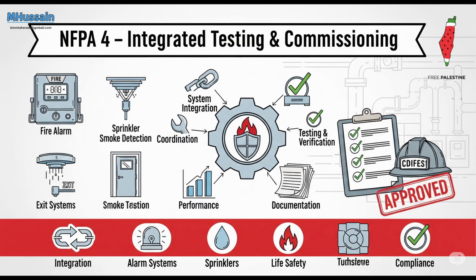And that's exactly what we're diving into today, a deep dive into NFPA 4, the standard for integrated fire protection and life safety system testing. This isn't just about individual components working in isolation. It's about making sure every single part of a building safety system works together seamlessly as one unified system. It's actually quite a story how this standard even came about. For a long time, this whole idea of integrated system testing was just a recommended practice. Just a suggestion. Pretty much. It was a chapter tucked away within NFPA 3, which mostly dealt with commissioning systems. So a good idea, people thought, but not something you had to do.